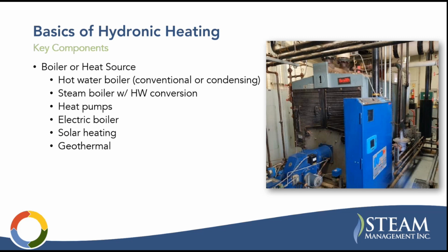Key components here, you're going to have a boiler or a heat source. That can be a hot water boiler, an old conventional boiler, or a condensing style hot water boiler. You could have a steam boiler with a hot water conversion, which is basically just a heat exchanger, taking heat from the steam, turning that into hot water. You can have heat pumps heating the water, electric boilers, solar heating, geothermal. And in many cases, some of these sources can just supplement the energy supply and not be the sole provider, but it's a very flexible system.